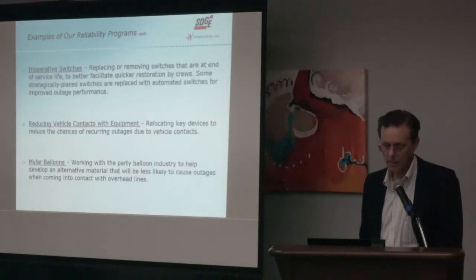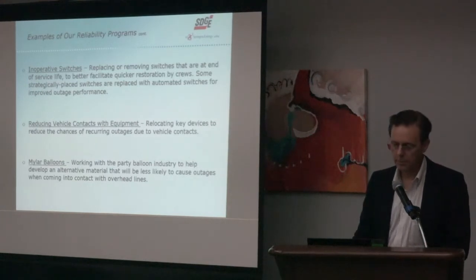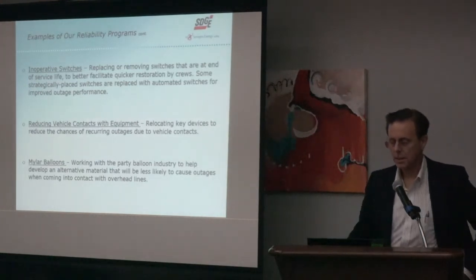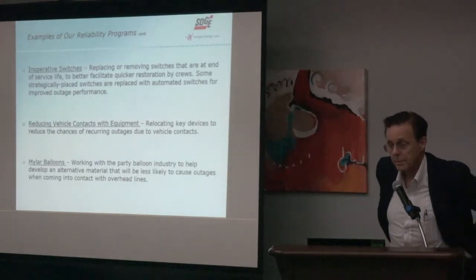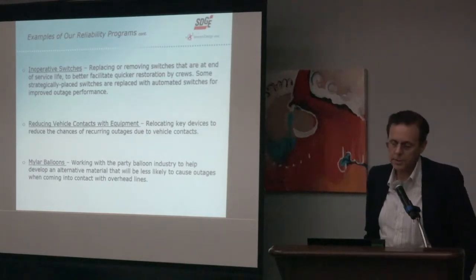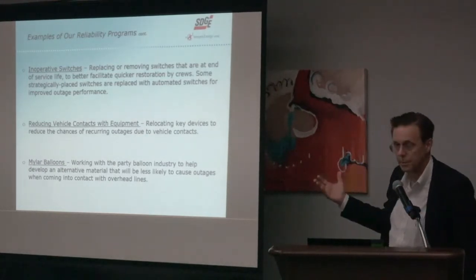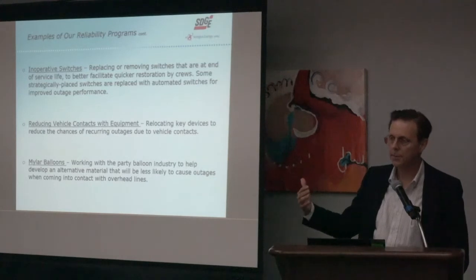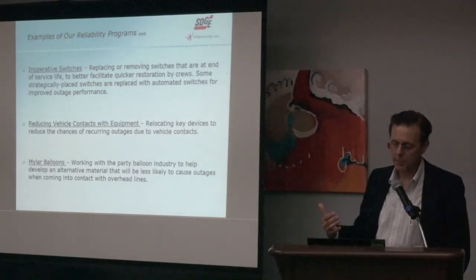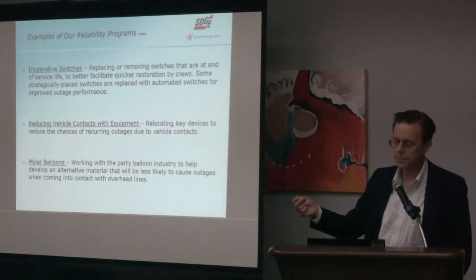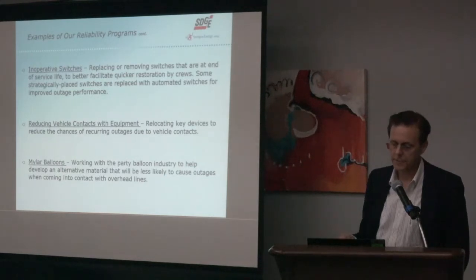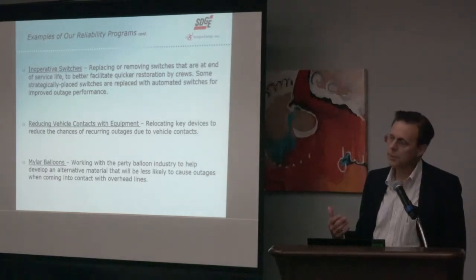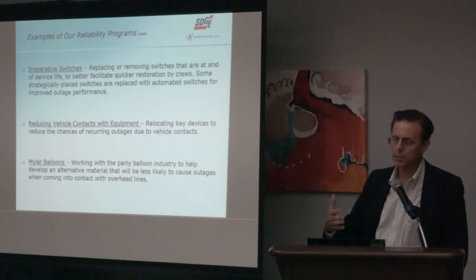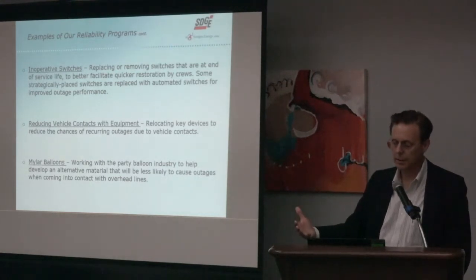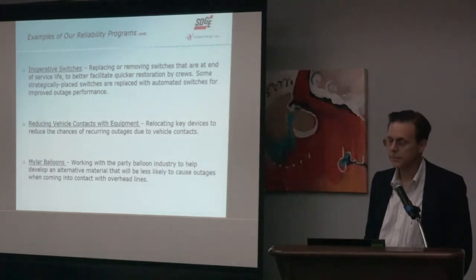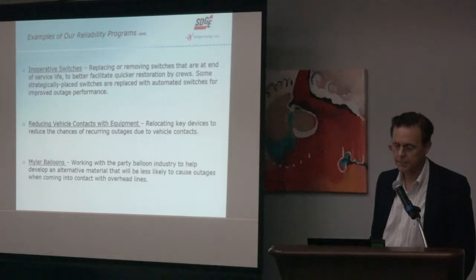Moving along, some additional examples: we have switches that have gone through a significant part of their service life and become inoperative. We call them DOE, do not operate energized. We have a program aimed at either replacing or removing those switches that have reached end of service life. This better facilitates quicker restoration by our crews because they're able to operate those switches directly without concern for employee or public safety.